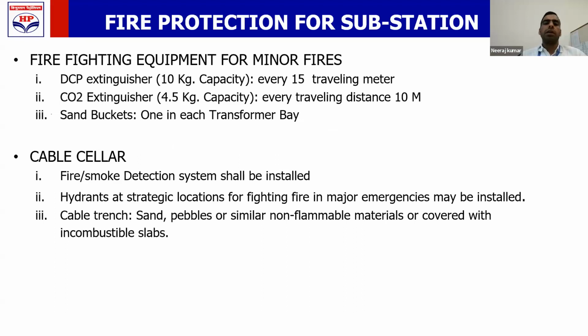Now, how should the firefighting equipment in a substation be? There are three things: DCP extinguisher, CO2 extinguisher, and sand bucket. All three are required in a substation if there is a transformer. DCP extinguisher, 10 kg capacity at every 15 traveling meters. CO2, 4.5 kg capacity every 10 traveling meters. Sand buckets are required, one in each transformer bay. So DCP and CO2 inside the substation at 15 and 10 meters, and sand bucket in the transformer bay.